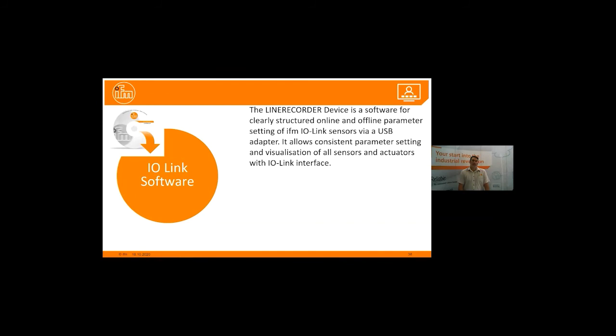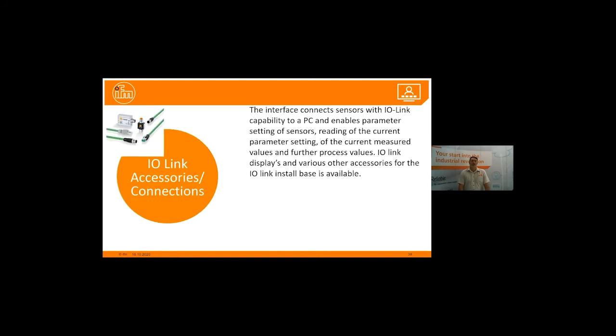LR device software is used to clearly structure online and offline parameter settings of an IFM IO-Link sensor via a USB adapter. It allows consistent parameter settings and visualization of all sensors and actuators via this IO-Link interface. The interface connects sensors with IO-Link capabilities to a PC and enables parameter settings of sensors, reading of the current parameter settings, of the current measured values, and further process values. IO-Link displays and various other accessories for the IO-Link install base are available from us.